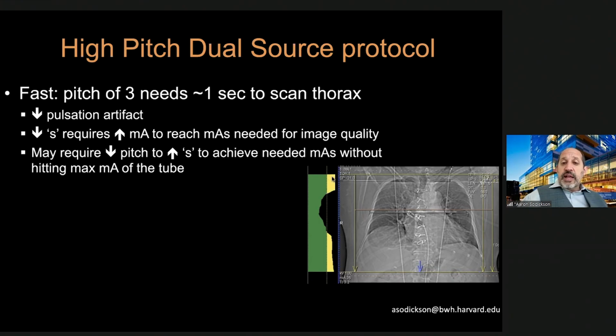On this scanner, the yellow represents areas of the body where we have hit maximum mA tube output limits. And so we're going to see more noise through these portions of the scan compared to this portion where tube current modulation is basically allowed to do its thing. But that's okay, because for this application, I would accept this tube current modulation scheme, even knowing that we're maxing out and we're getting more noise through the shoulders and the diaphragm.